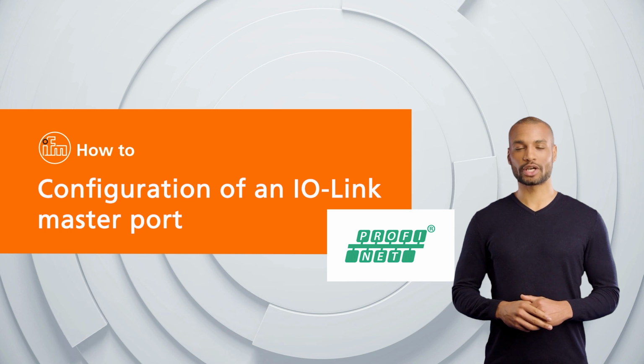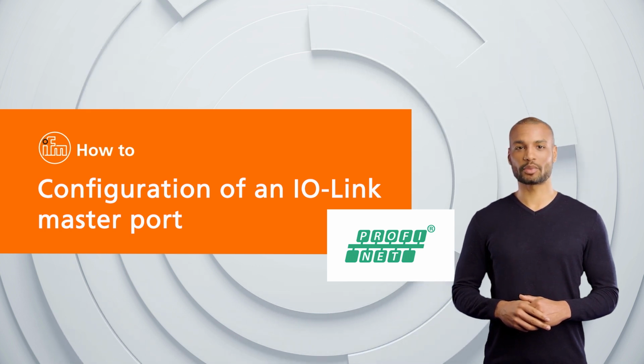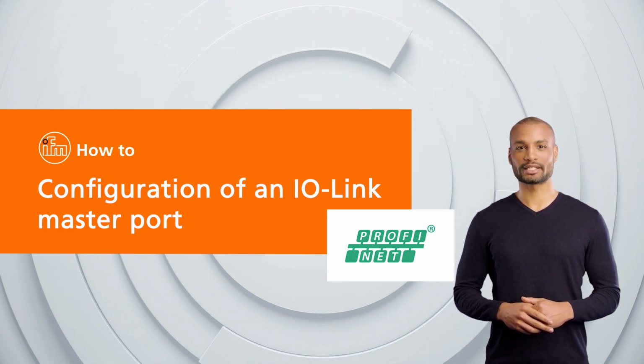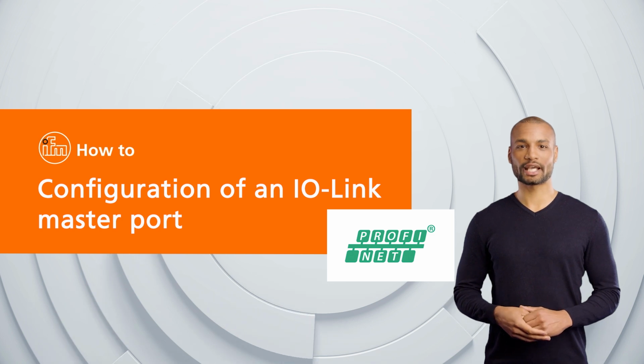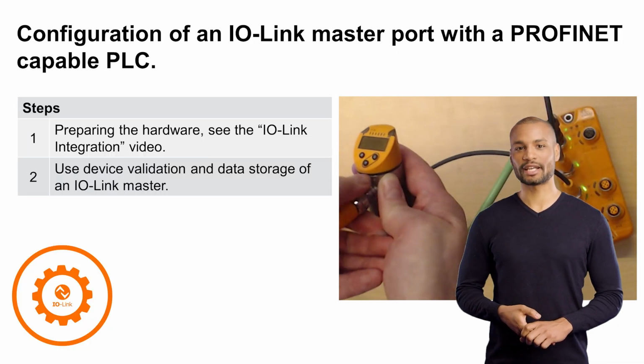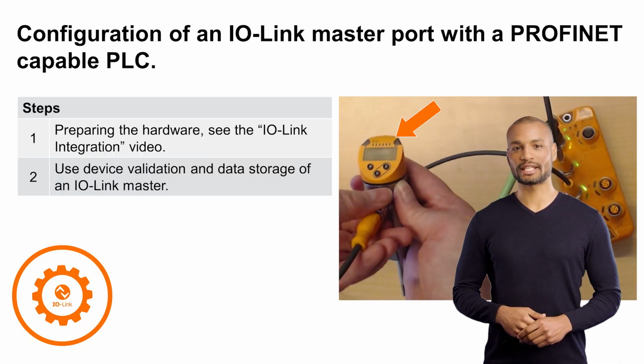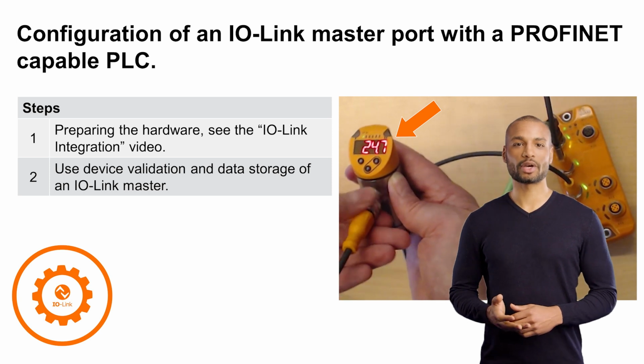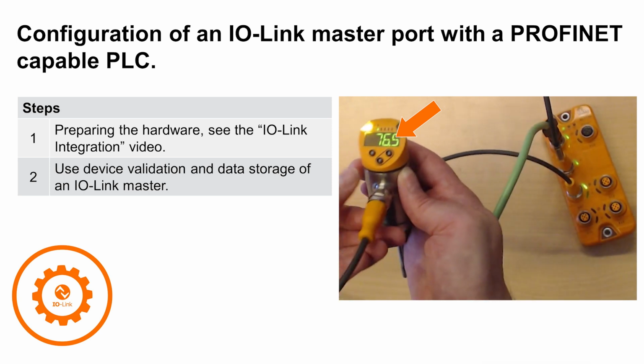In this video, we show you how to configure an IO-Link master port with a PROFINET capable PLC to use device validation and data storage. By activating this function, the IO-Link device is automatically checked and parameterized by the IO-Link master.